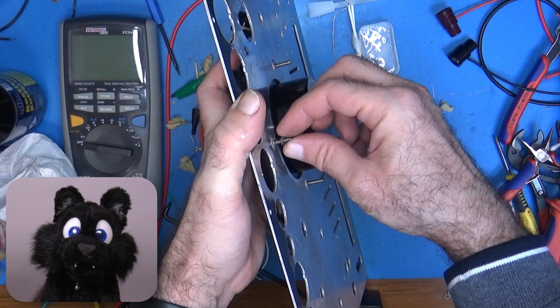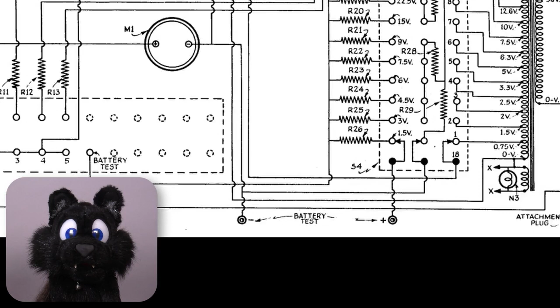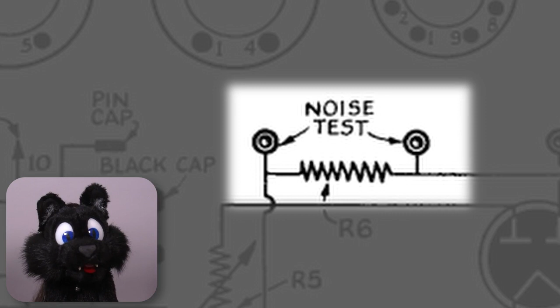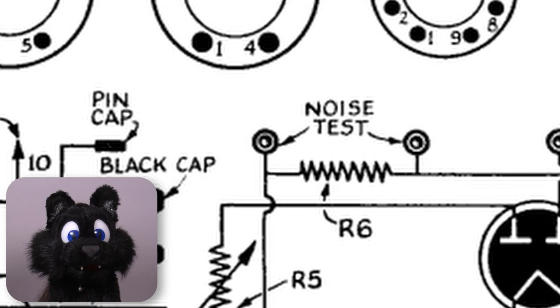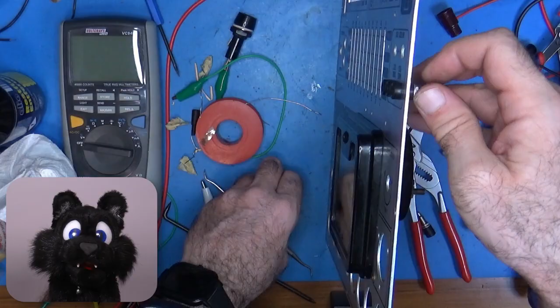And now, reassembly, starting with the meter and main buttons, including the wiring loom. There are 5 external connectors for battery testing, the leakage test, and to pull out audio for a noise test, which is pretty much the voltage across the current shunt in the test circuit. The old contacts are, like with the VTVM, a strange version that is not very useful, so I replaced those with 4mm banana jacks too.